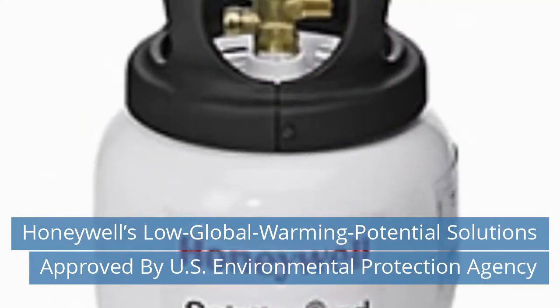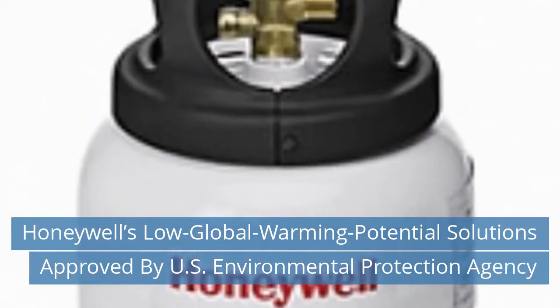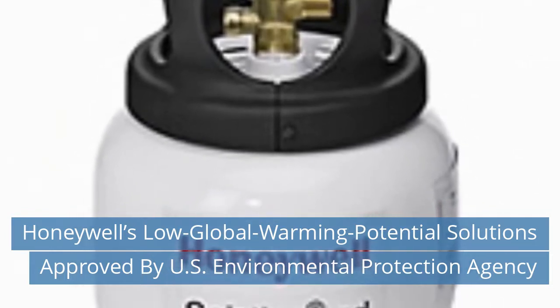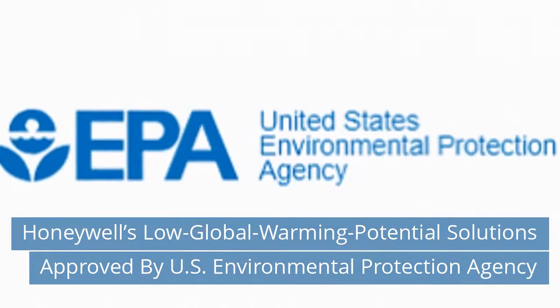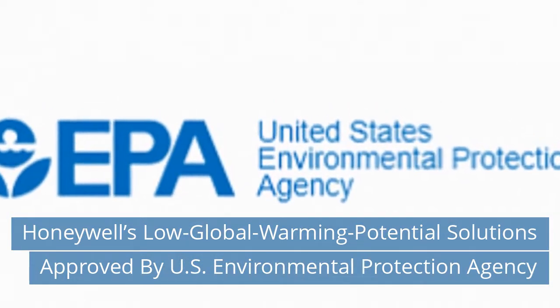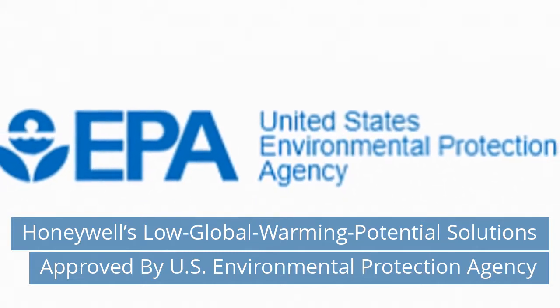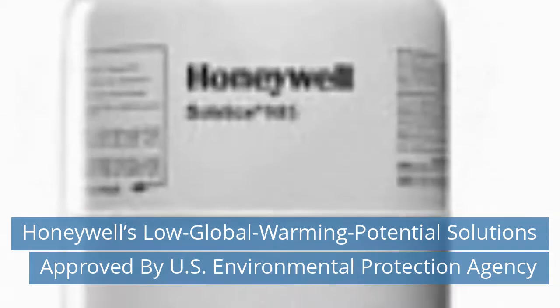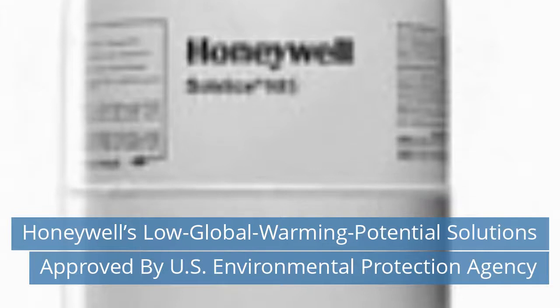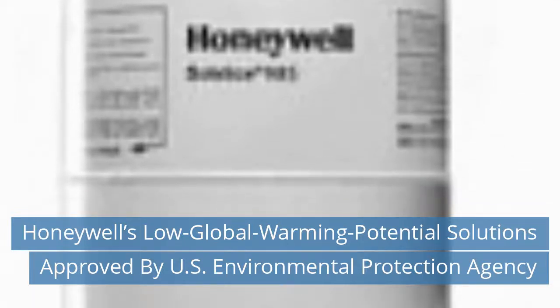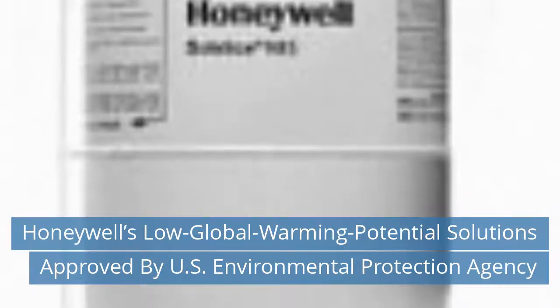Honeywell today announced the U.S. Environmental Protection Agency, EPA, has recognized its environmentally preferable Solstice refrigerant technology for use in centrifugal and positive displacement chillers and industrial process air conditioning systems. Solstice N15, R515B, a non-flammable, low global warming potential, LGWP, refrigerant, was listed by the EPA's Significant New Alternative Policy Program, SNAP, as acceptable for use in centrifugal and positive displacement chillers and new industrial process air conditioning systems.